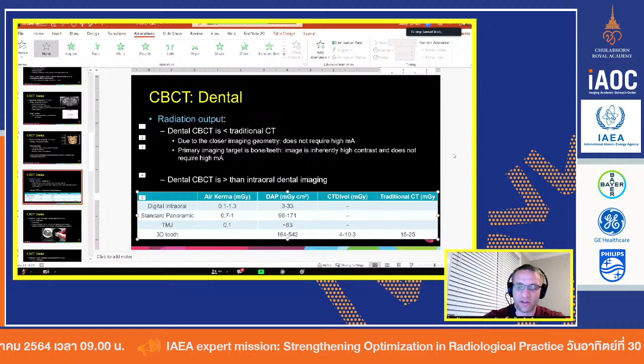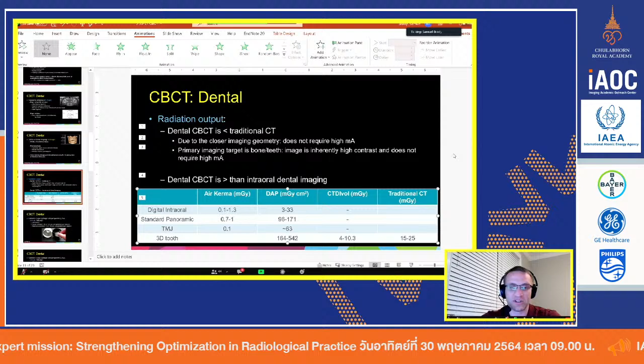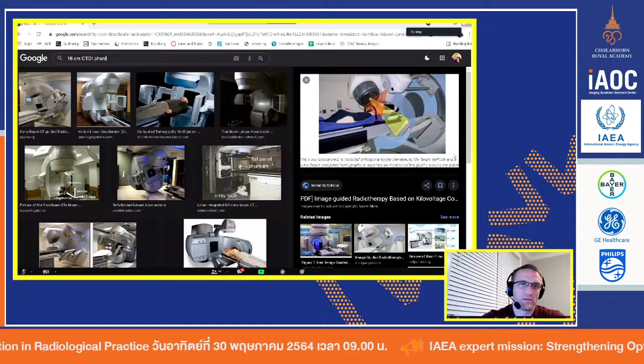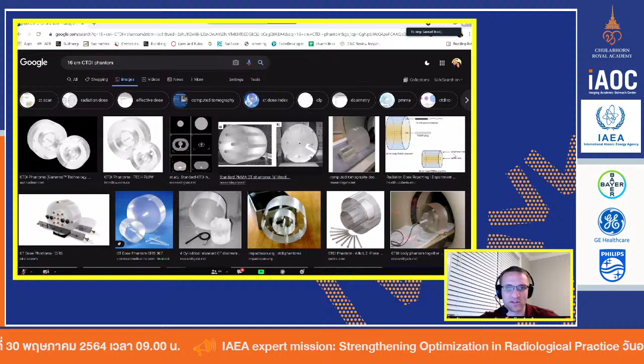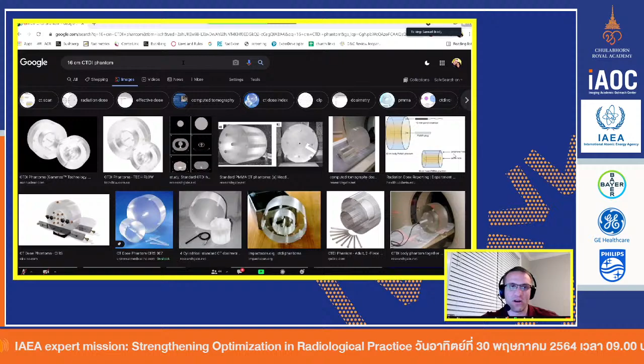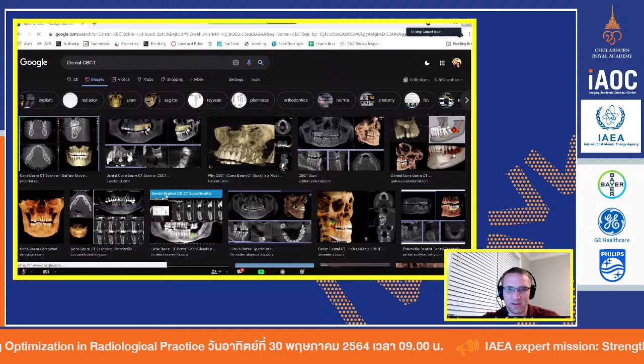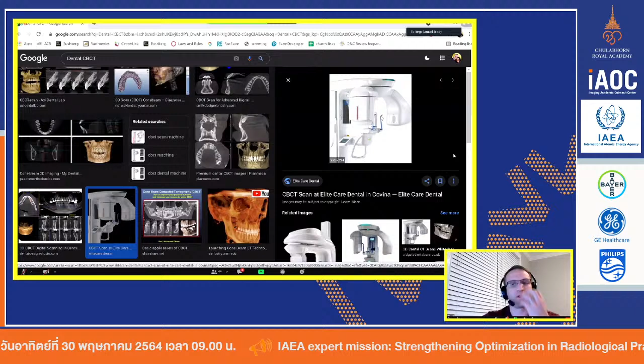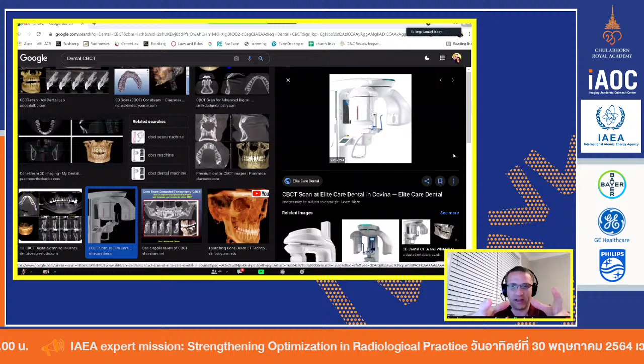And the way these systems are measured, or the way we calculate CTDI, is the same. We're still using the same phantom that you see on my screen, the 16 centimeter one, the smaller of the two. You place the same phantom on the machine. What you do is take this little blue piece out where the patient bites. You just pop that off, and you place the CTDI phantom on it, as if there was a head there. And you place your ion chamber in it, and you spin it around.